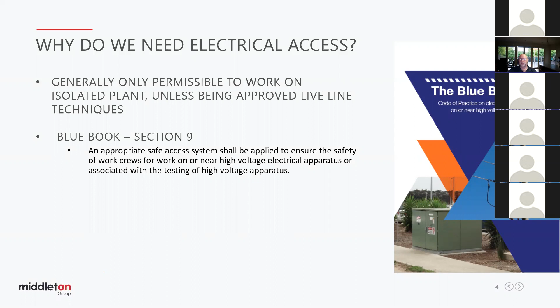Section 9 says an appropriate safe access system should be applied to ensure the safety of work crews for work on or near high voltage electrical apparatus, or associated with the testing of HV apparatus. I'm going to talk a bit about HV and LV in this discussion, because I think the same principles apply. Unless the risk can be managed appropriately, the power needs to be off—that should always be the first approach taken. If we remove the electrical hazard altogether, it's safer for the workers. Of course, if you're in the electricity supply industry or some other industry where the power needs to stay on, you've got to think about the impact of taking the power off.